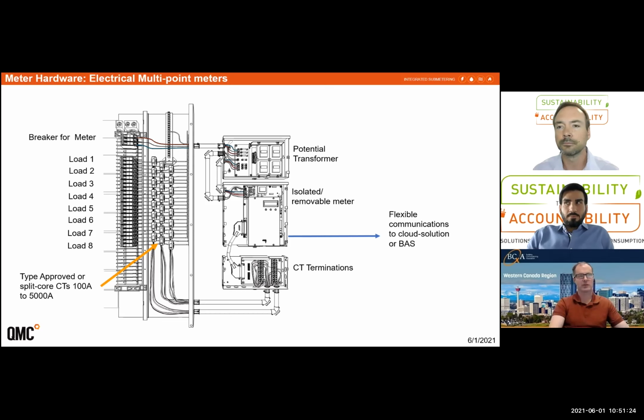Do you guys utilize split core or are they solid core? The majority of the time, probably 90% of our deployments are solid core CTs for a few reasons. Three reasons. One is any billing application needs to be a solid core CT. The solid core CTs are usually less expensive. So for new construction applications, it's usually cheaper to use them anyways, because you don't need that split core technology for a retrofit. And lastly, they are more accurate.